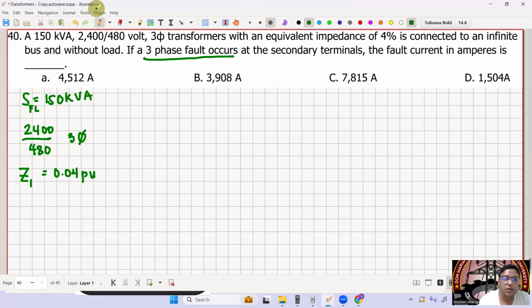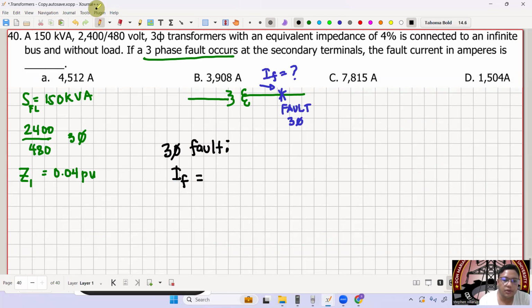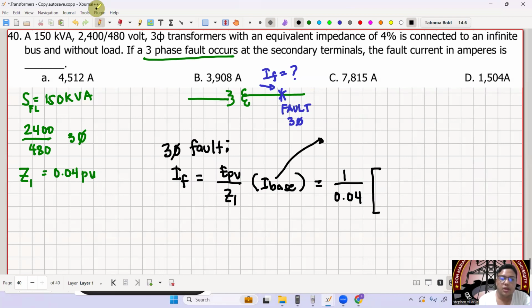Now, if a three-phase fault occurs at the secondary terminal, so kung i-drawing natin yan or i-imagine natin yan, ganito siya. So ito yung transformer, magkakaroon daw dito ng fault. And anong klaseng fault? A three-phase fault. So calculate the fault current in amperes. So ano daw yung I fault dito? Okay? So take note po, three-phase fault yung ating fault. So take note po for fault current for three-phase fault, that is your E per unit over Z1. Okay? Ayan. So, pero multiply na natin ng base kagad. So, since alam na natin na per unit times base is the actual na. So, therefore, this is now 1 all over 0.04 multiplied by your I base. So, saan natin ito kukunin? Dun sa rating. Okay? So, rating on the secondary side.